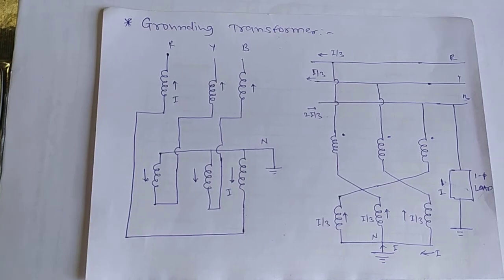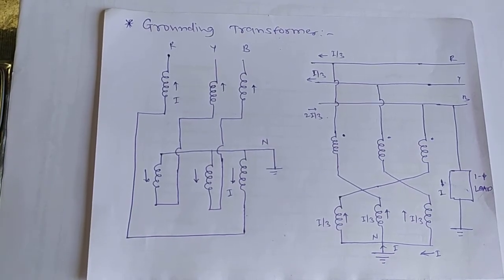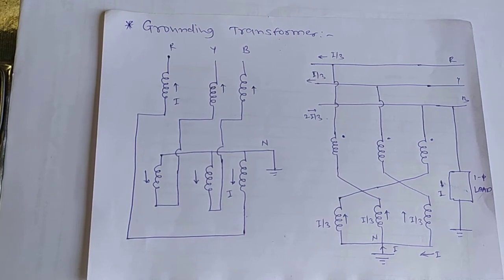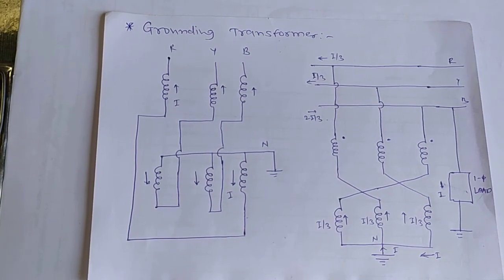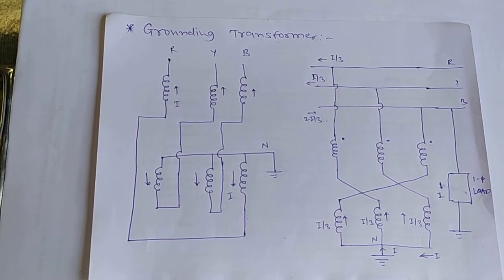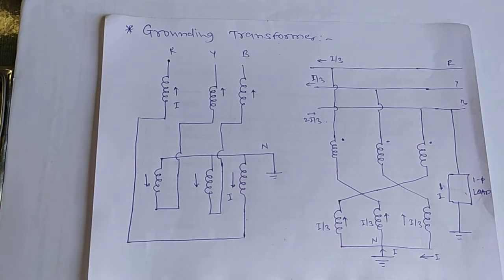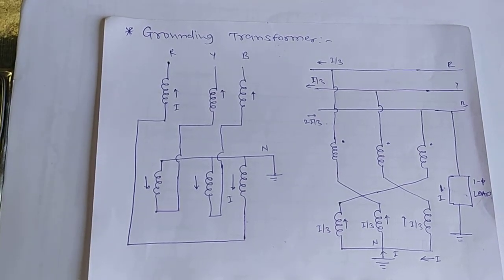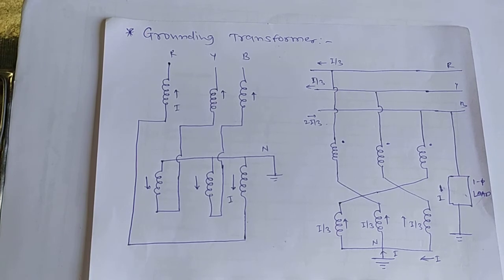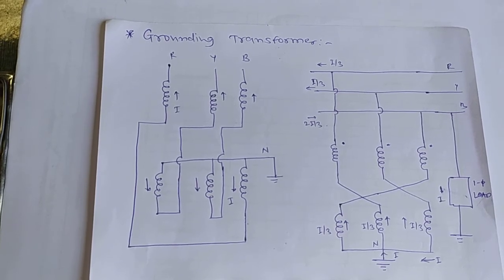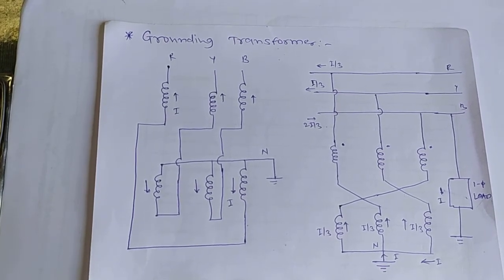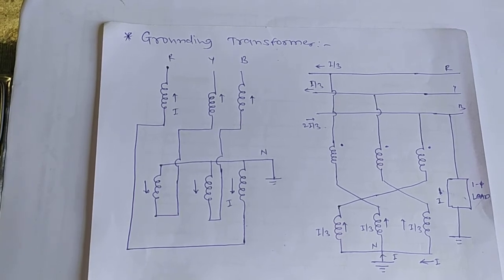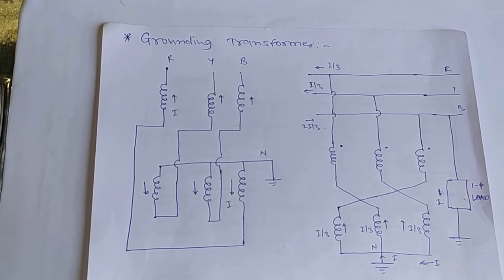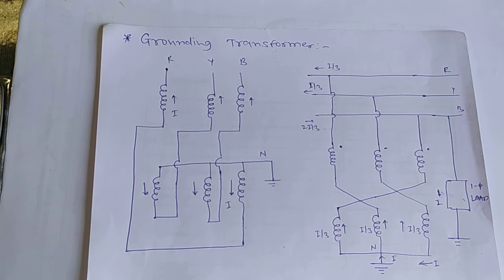The next one is the grounding transformer. To create a neutral point on a 3-phase 3-wire system, to change it into a 3-phase 4-wire system, this can be done by means of a grounding transformer. It is a core type transformer having 3 limbs, built in the same fashion as that of a power transformer.